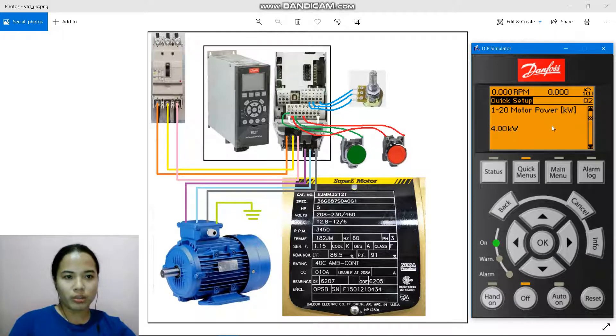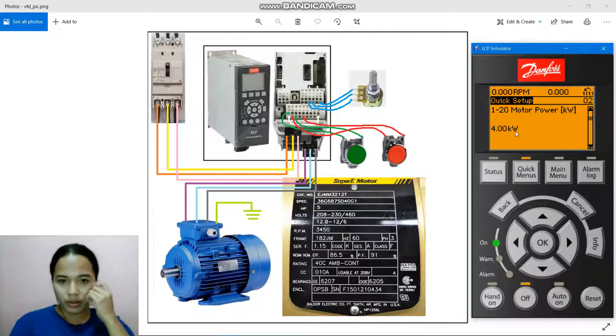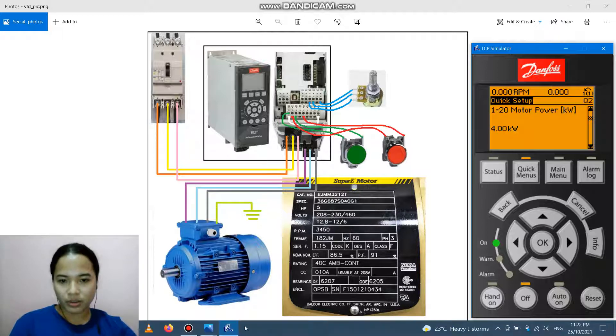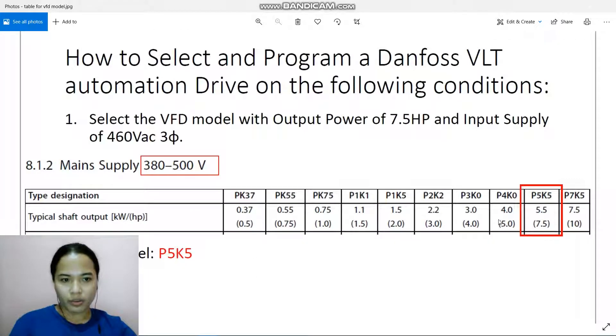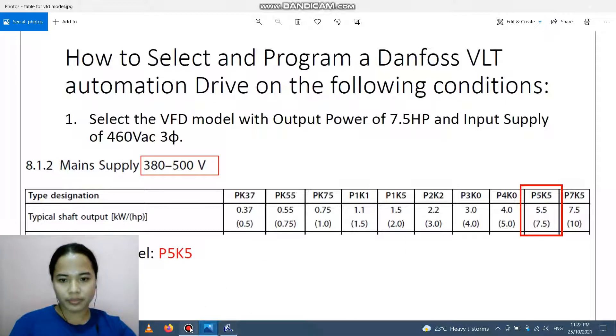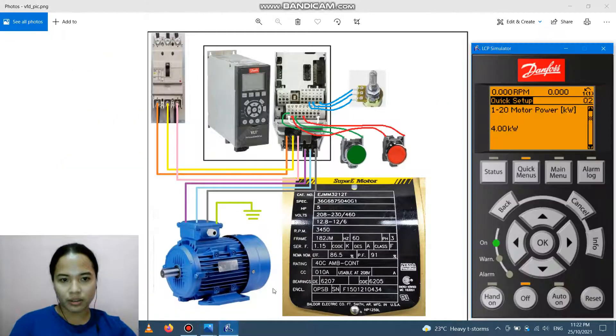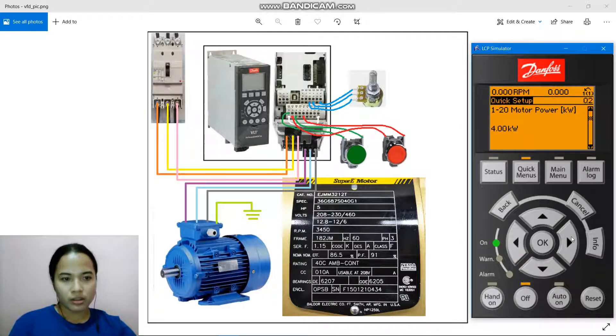In parameter 1-20 Motor Power (kilowatt), in order to know what to input here, we refer to the motor nameplate. We have horsepower 5. According to the table, horsepower 5 corresponds to 4.0 kilowatts. It's already set to 4.0, so we proceed.